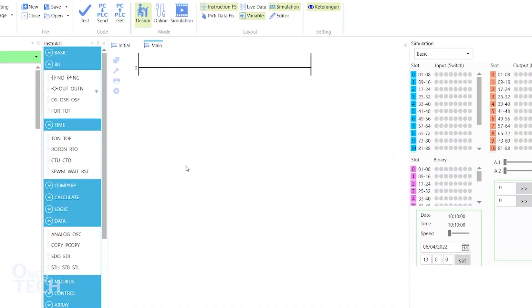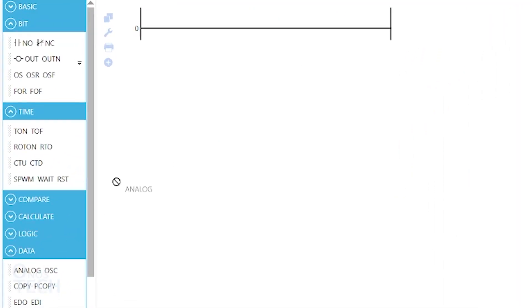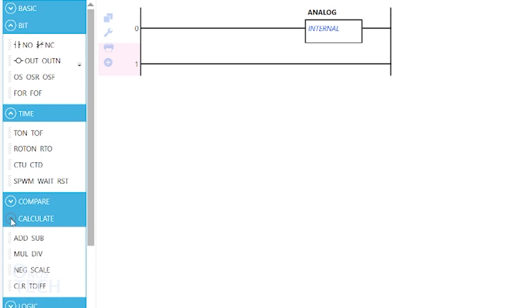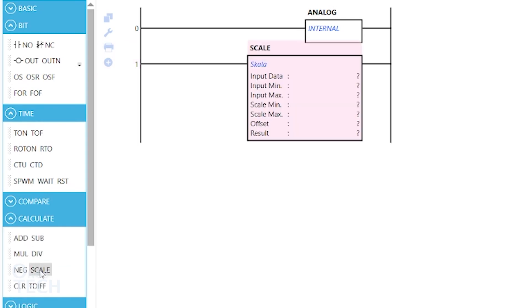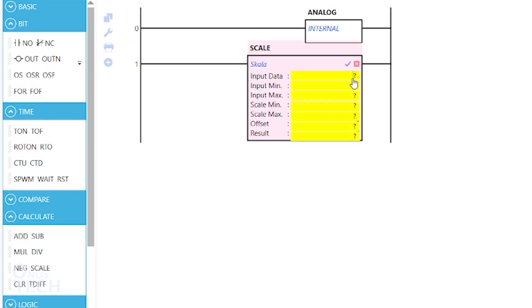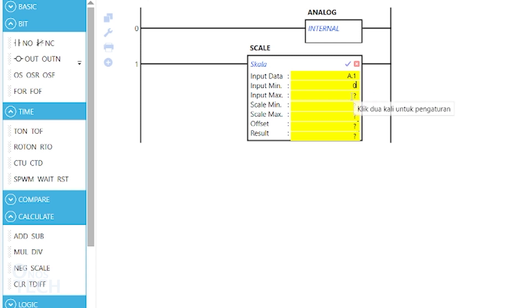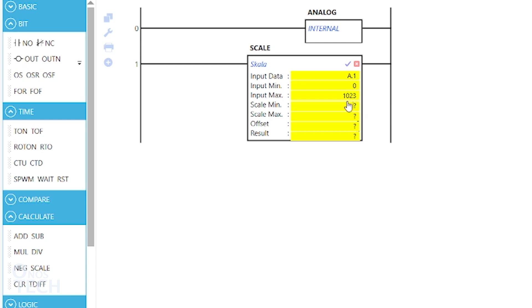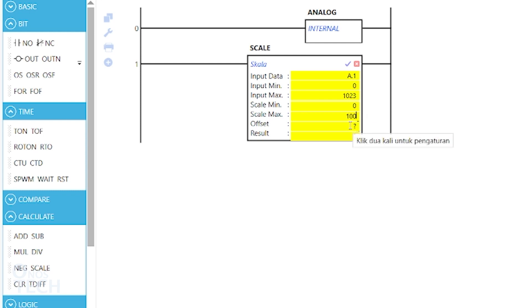Insert an analog and a scale instruction into the ladder diagram as before. Set the scale input data to A.1. The input min to 0. The input max to 1023. The scale min to 0. The scale max to 100. The offset to 0. And the result to I.1.